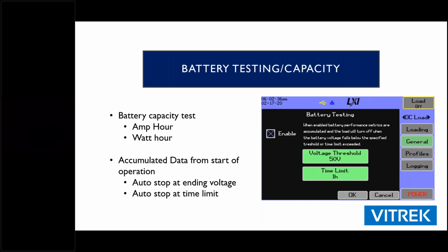This is something we talked about before. If you wanted to do a simple battery test on capacity, you're going to set either a time limit or a voltage threshold limit. In addition to the loading, which will be done on a different screen, you're basically going to set it up, turn the load on, and come back to an amp hour or watt hour capacity based on the profile you choose to load the product at. You're going to accumulate data, everything is stored there, and it's a nice built-in feature.